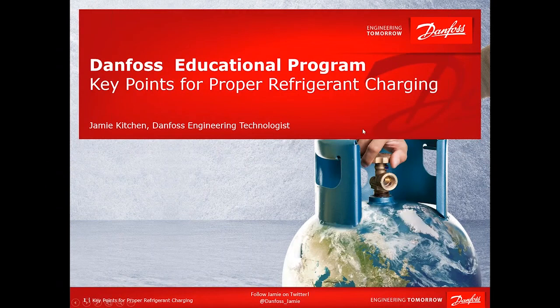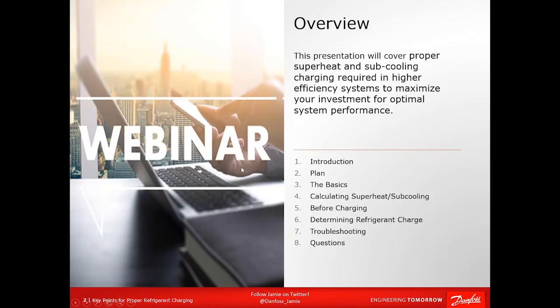As Michael laid out, high-efficiency systems in particular really rely on a correct refrigerant charge — meaning charging according to the manufacturer's recommendation. There are two key points to system efficiency, really the underlying foundation that determines how well a system performs. One is airflow, and the other is refrigerant charge, and they're in that order.